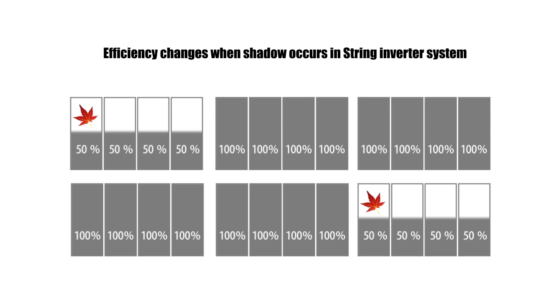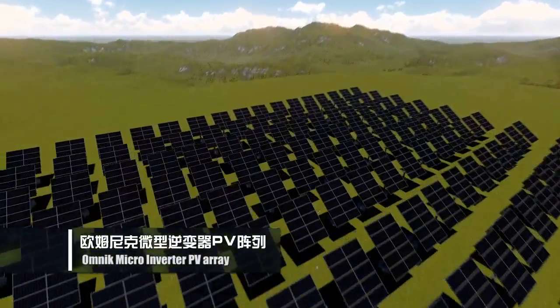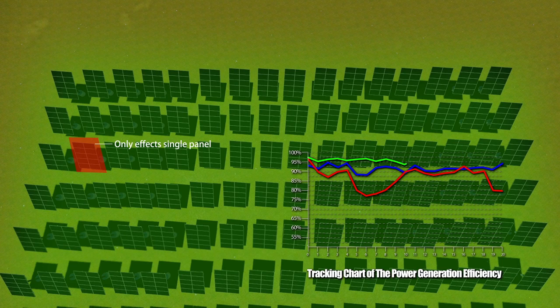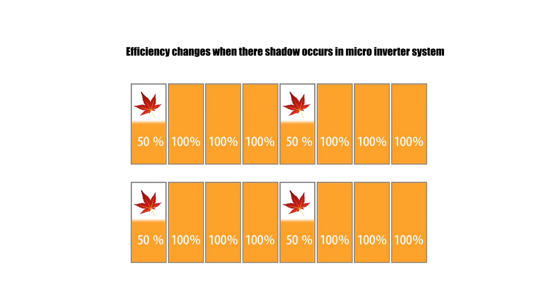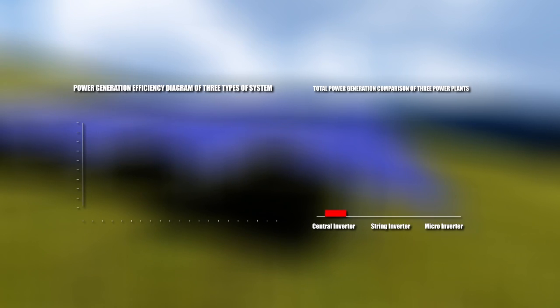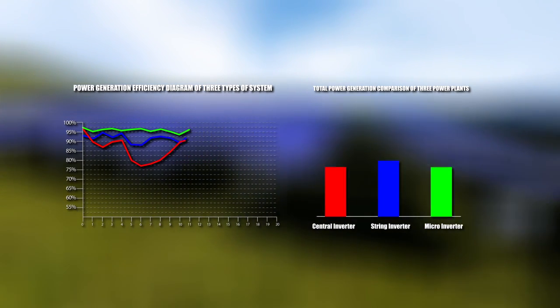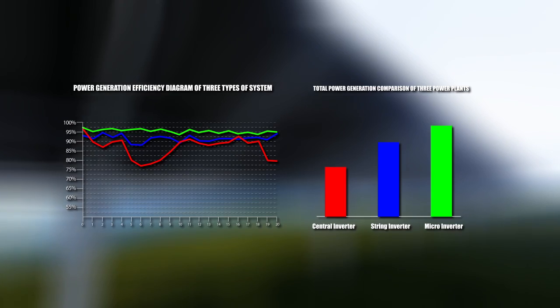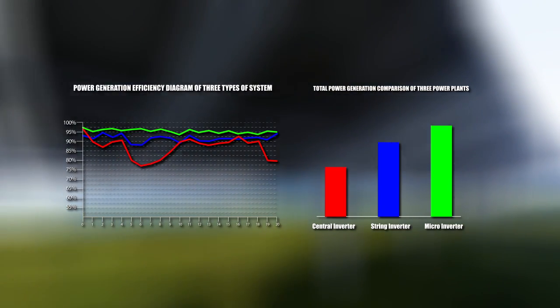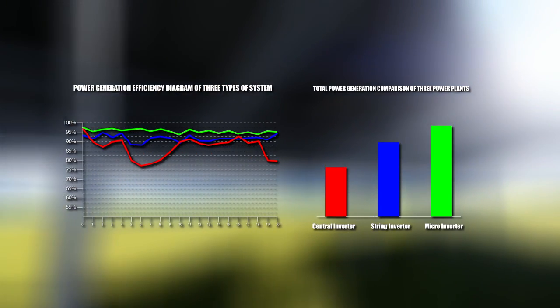With micro inverters, there will be 2,000 MPPTs for a 500-kilowatt project. Each panel works at its own maximum efficiency — shadows, different brands, tilt angles, and other factors will not influence other panels. In conclusion, considering total power output with all parameters included: central inverters generate relatively less electricity, string inverters generate more, and micro inverters generate the most.